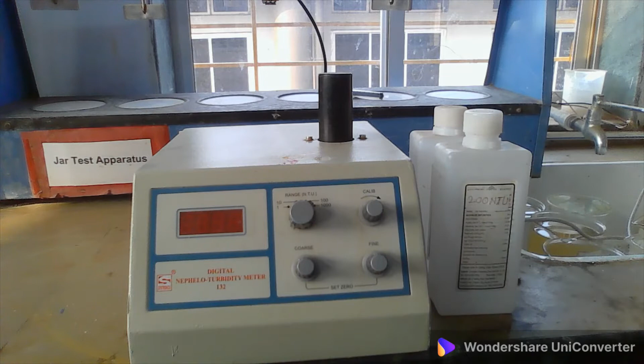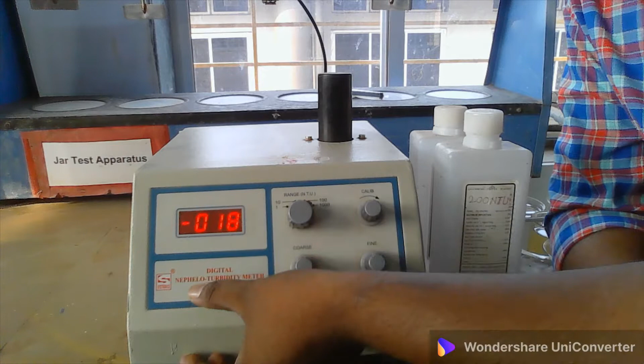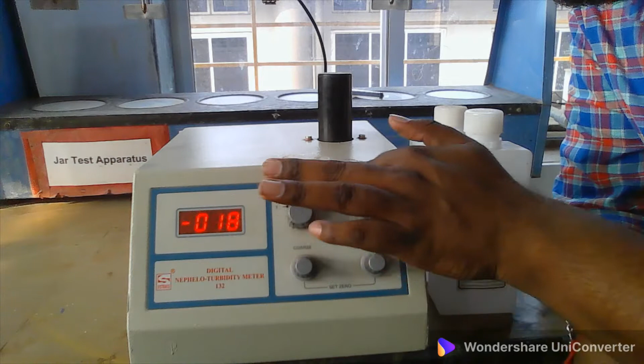Here you are able to see that different knobs are there. In this panel you are going to see the display of our turbidity. This is the digital nephelometer turbidity meter, the name of this instrument. The turbidity values you get with this instrument are in NTU, because nephelometer is the name of the instrument, and turbidity units determined by this nephelometer are known as nephelometer turbidity units. Here we see the range switch.